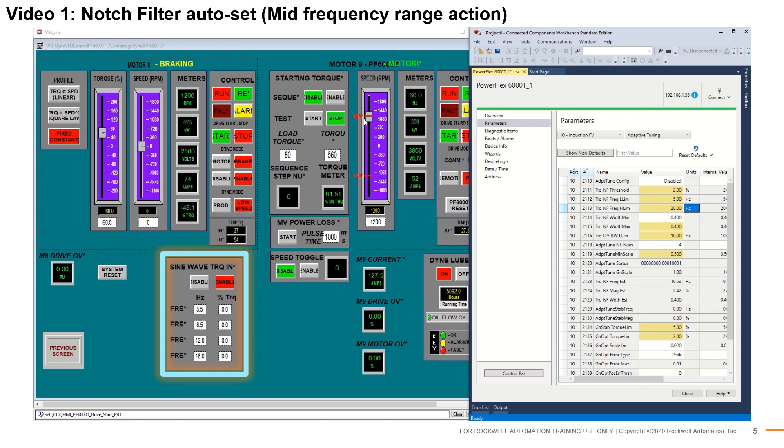On the left, a PLC program's interface is shown. The section of interest is the sine wave injection portion. We will be injecting three different frequencies and picking up one characteristic frequency. All four notch filters will be set at the end. On the right is the CCW interface you may already be familiar with. We will be focusing on the adaptive tuning and torque filtering set of parameters.